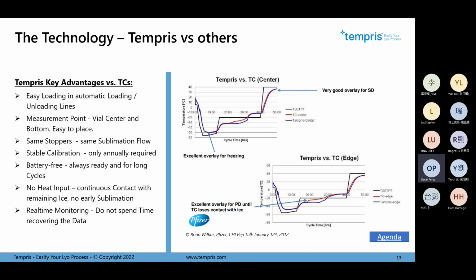Moreover, we have one sensor per vial, so all the surrounding vials around this measurement point will be vials with liquid, not special holders, batteries, or other parts that other technologies have. So we are measuring at a point where the surrounding vials are in the same condition, making us more accurate about what's really going on inside the freeze dryer regarding temperature.